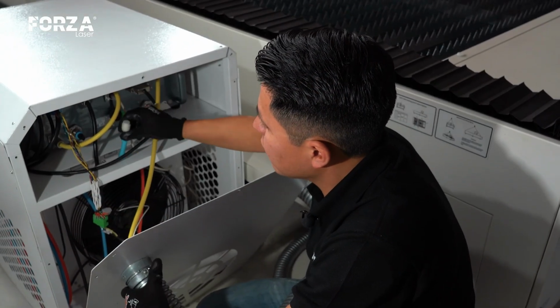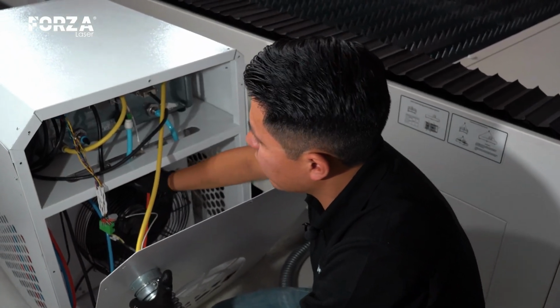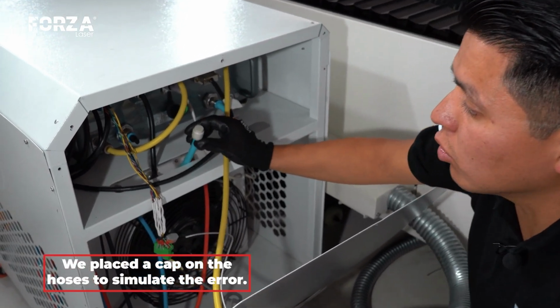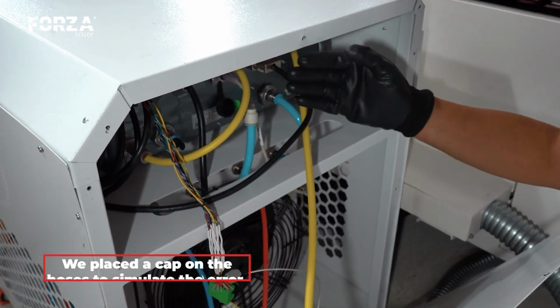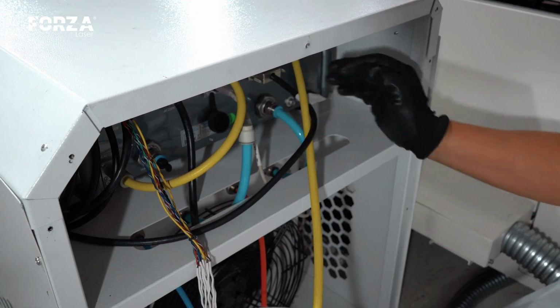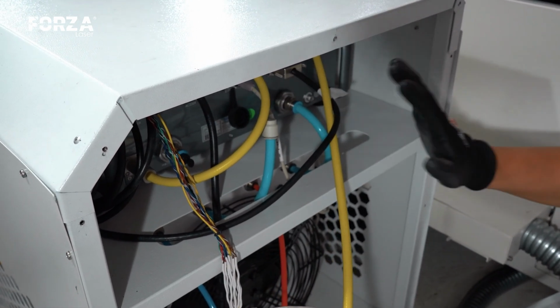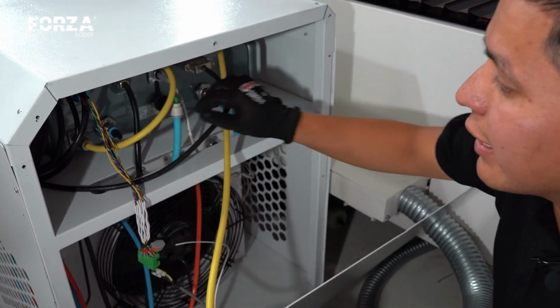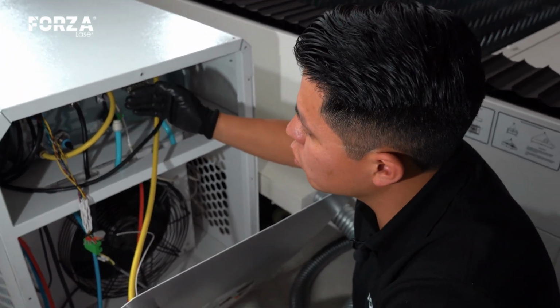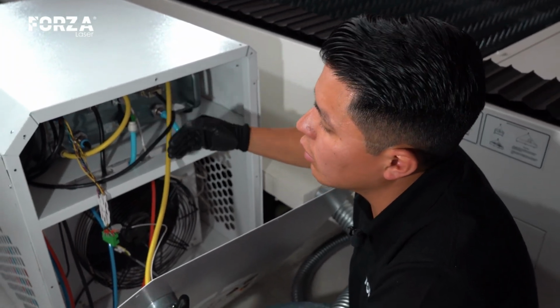As we can observe here, we have placed a cap on the chiller's water outlet hose. Evidently, with this cap, there's no water coming out, and consequently, no water will be entering either. But if either of these two hoses is crushed or blocked with the cap, there will be no water flow. This will then trigger an alarm on the chiller.